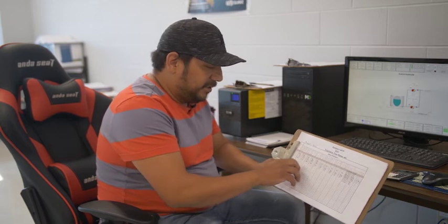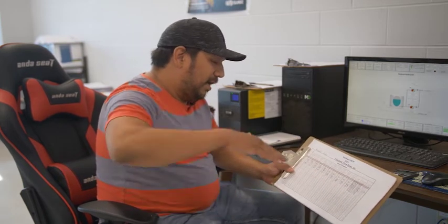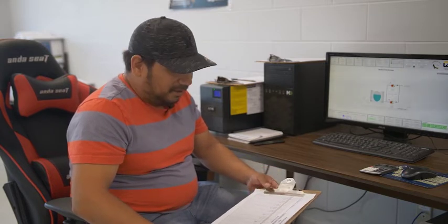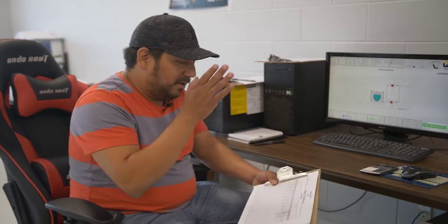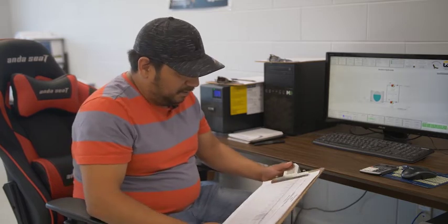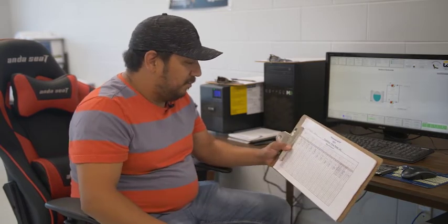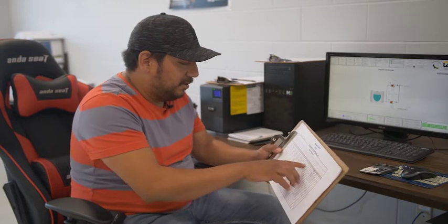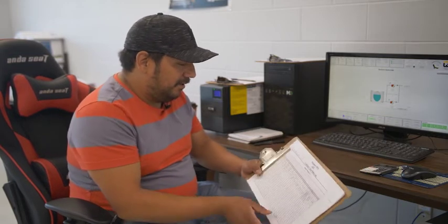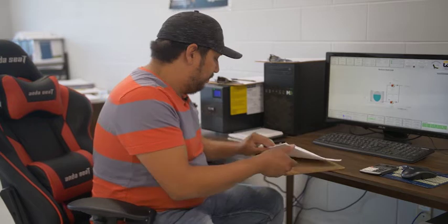With regards to the pressures, like I mentioned, we didn't do the checks on a nanofiltration unit, but again, this is basically just pressure checks, and we're looking to see if anything has risen to a critical point where we're going to need to do what they call a clean in place on the RO units. And it's a very extensive clean. It usually takes about a full day to do that clean in place on one train. And in this instance, we have 2 trains. So if we ever have one down, then we can concentrate on that one, work on the other one, and go from there, right? But for the most part right now, we're on top of everything. Our pressures aren't critical. Usually if we see 150 PSI somewhere, then we know it's definitely time to do a clean in place at that point.